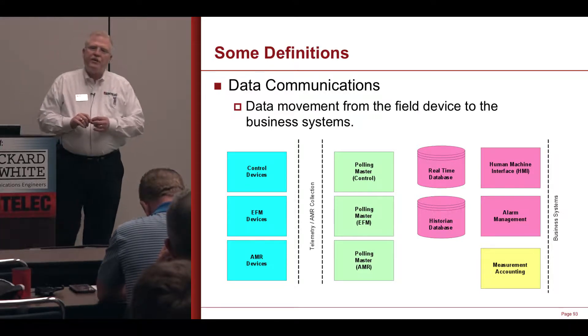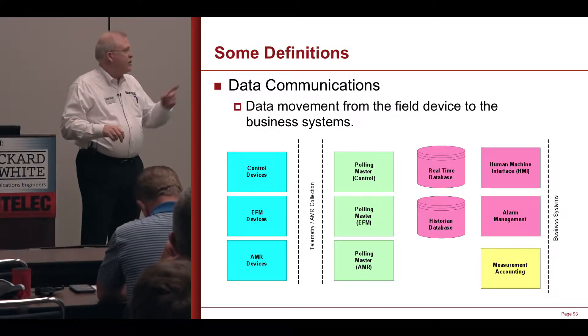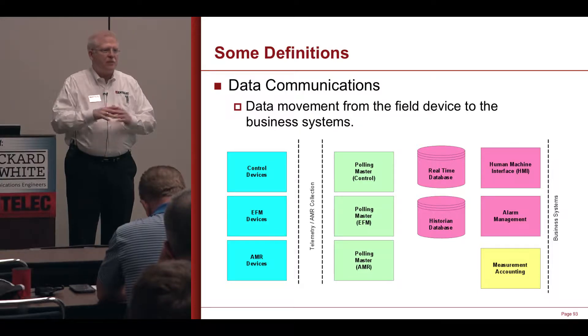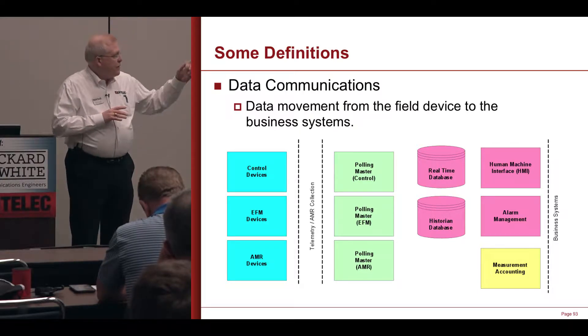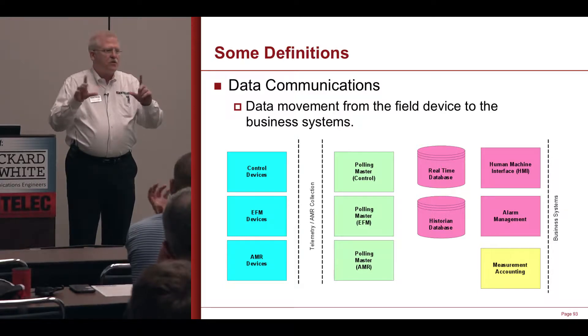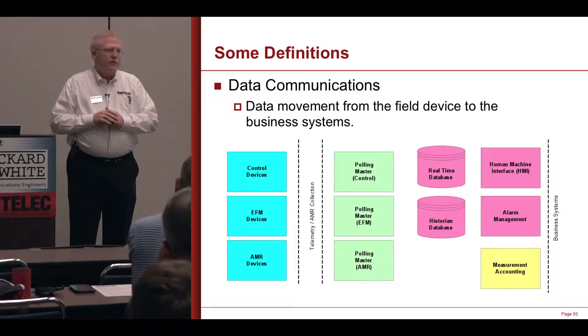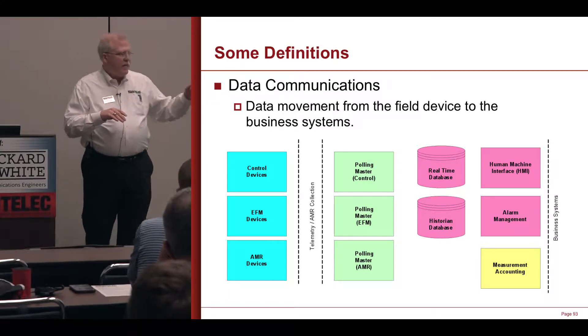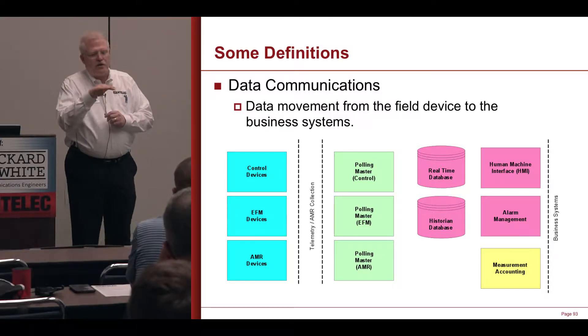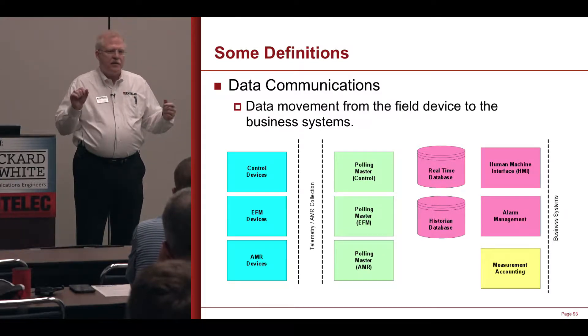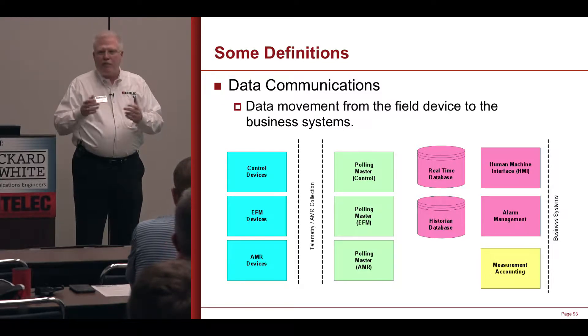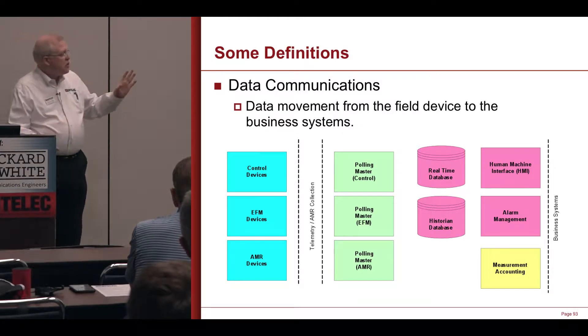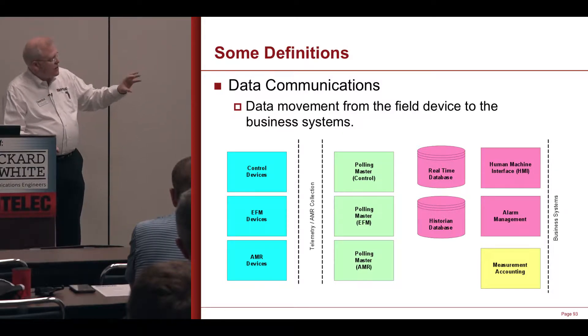The historian keeps an image of every data value I got up to the real-time database, so I can do trend charts and see what the pressure was over a period of time. The HMI is the package we use to build all the screens with pretty graphics, circles, and numbers so we can understand what's going on in the process. The alarm system monitors all these values to see if they go outside of bounds, then sends a notification that you might need to do something because the process is out of where you want it to be. Those are the basic pieces of a SCADA system.